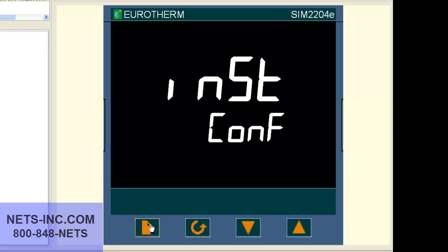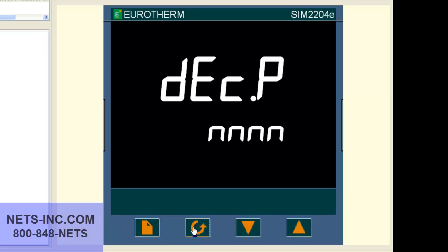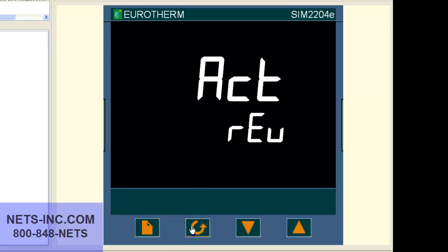Now press the page button repeatedly until the display reads ACT REV. Now press the up button to change the displayed value from REV to DIR.